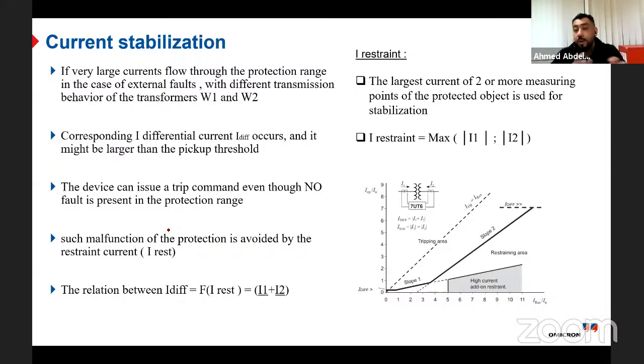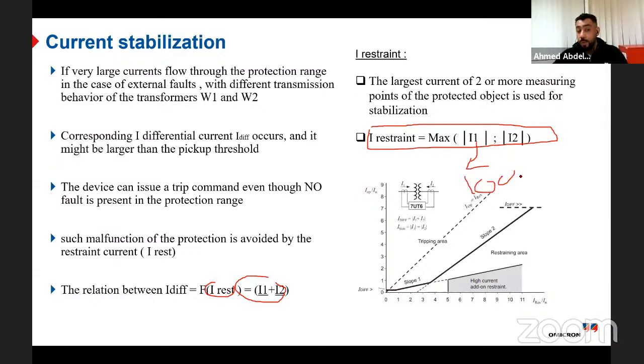And this is in general what I said, that I have a relationship between the differential current as a function of I restraint, which is equal to I1, I2. And I restraint here is equal to the max of I1, I2. This is just an example. So that's why we need to say that every time, in order to know the exact formula or equation for the restraint current, you need to go back to the relay manufacturer. This is the Siemens relay, 7UT6. So it has a maximum of I1 and I2. So for example, if I have I1 here equal to 1000 and this is 1500, it will take the maximum one to have the highest security.